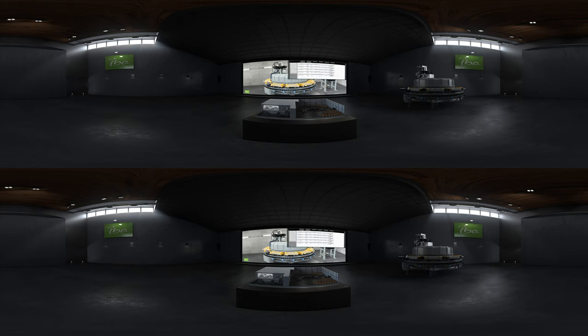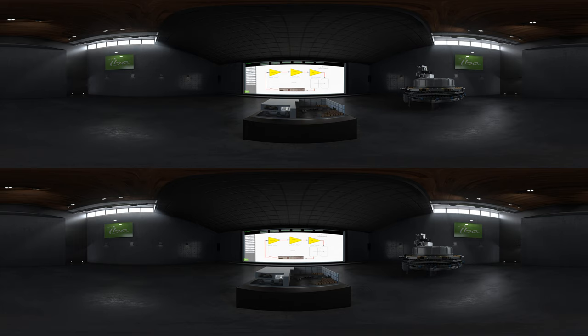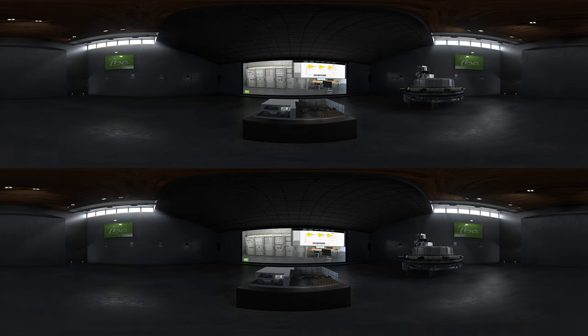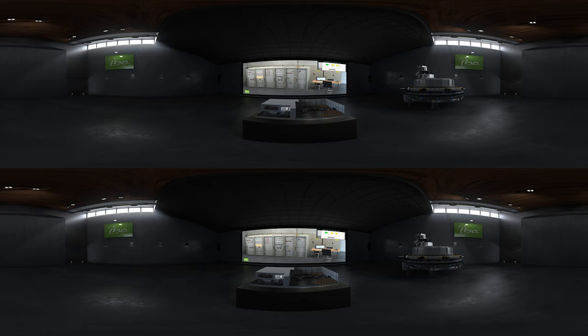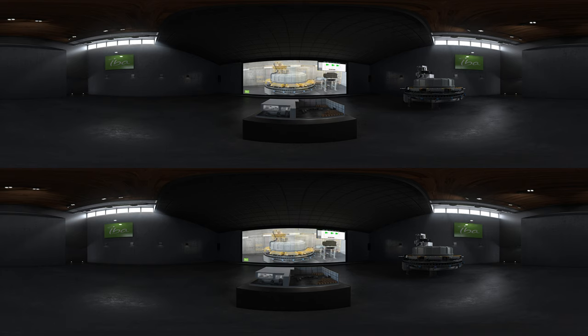As you can see, the activation of the radio frequency system happens in four different stages. A small signal is generated by the low-level RF rack. The signal is amplified by the pre-driver, then amplified a second time by the driver amplifier. And finally, a last time by the final power amplifier located on top of the cavity. This final amplifier is coupled to the cavity to generate the electric field in the machine.